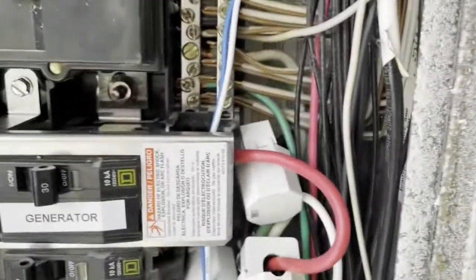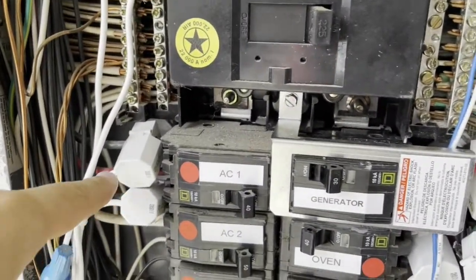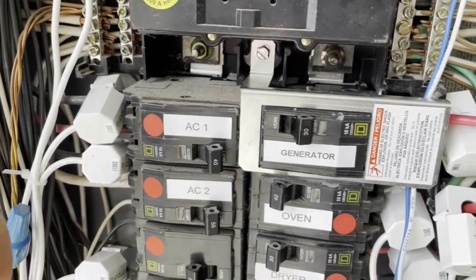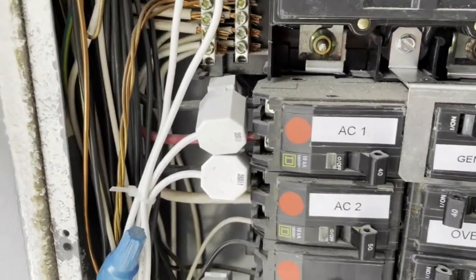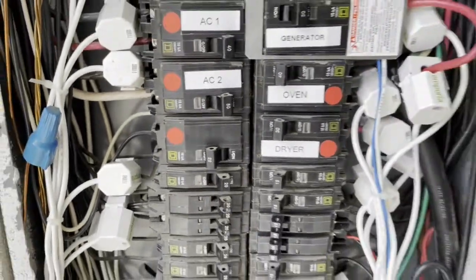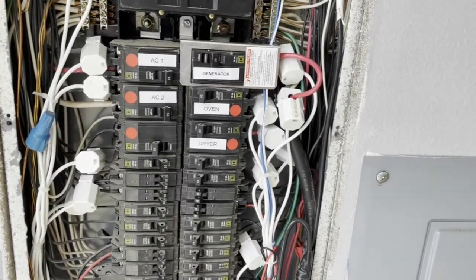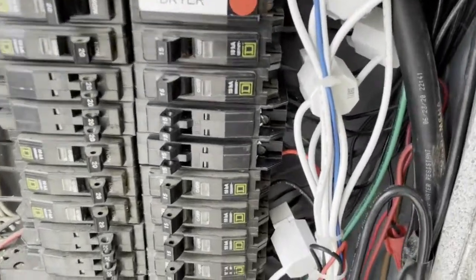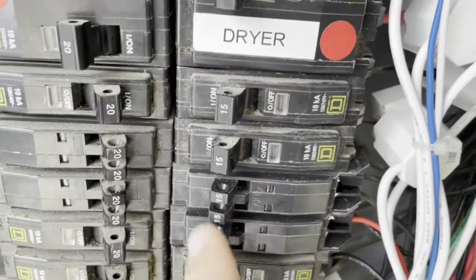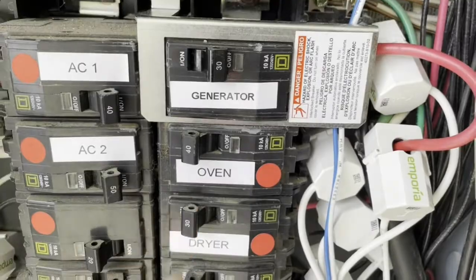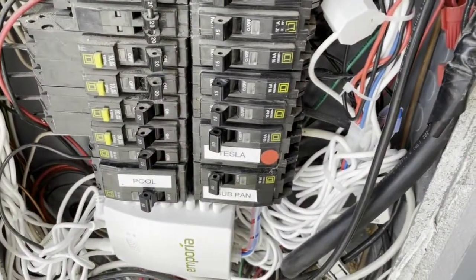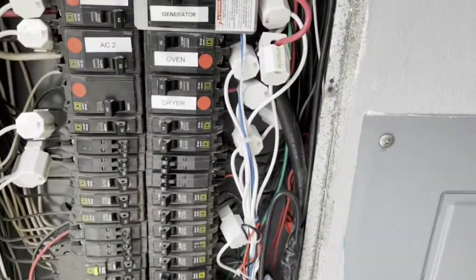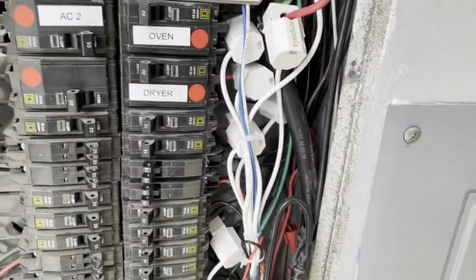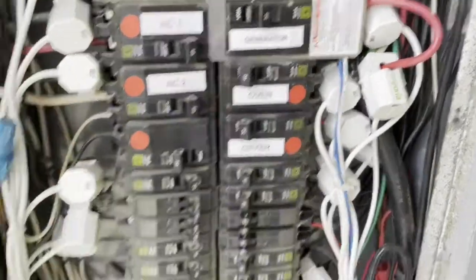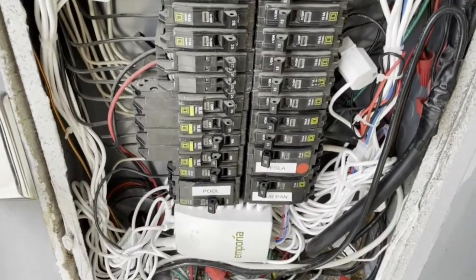So you start connecting and clipping these cables. Of course, everything must be turned off. You connect these clips, sensors, over the hot line in every circuit breaker you want to monitor. It's important to know which circuit breaker feeds which circuit, because I'm not really interested in the 15 amp ones since those are usually lights. I'm more interested in my oven, dryer, ACs, EV charger, and pool equipment. So I chose 16 circuits that were important for me, and connected each one without losing track of which cable goes to the box.